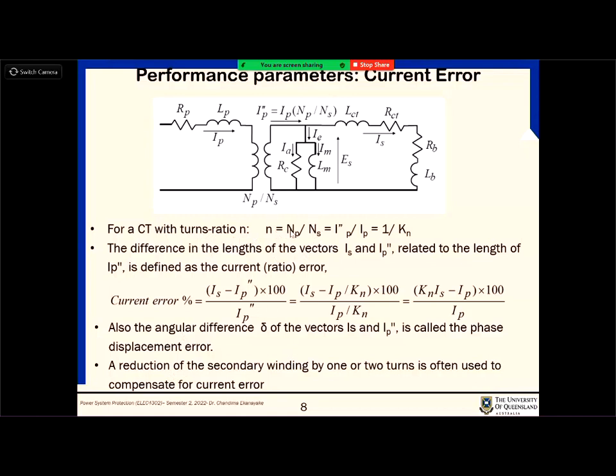You can see that the turns ratio is given as NP divided by NS, or the current ratio between IP and IP double dash, see? And it is defined as a constant, 1 upon Kn. Now, if you want to calculate the difference between IS and IP, sorry, we define the error as the difference between IP double dash and IS, as shown here. That is the error, right? IS is what you measured, and IP double dash is what the measurement would be if it were correct. So the difference between them will give you the error.